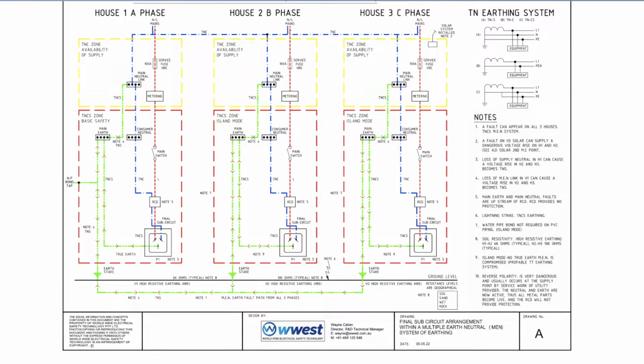The drawing we're looking at is the final subcircuit arrangement within the multiple earthing neutral (M.E.N) system of earthing. We've called it drawing A, as you can see down here. This is a typical layout of the M.E.N system across three houses. So we've got three houses, one on each phase.